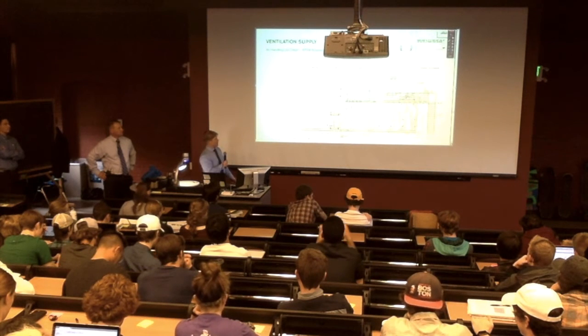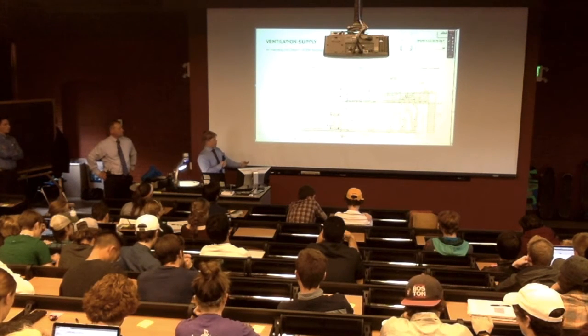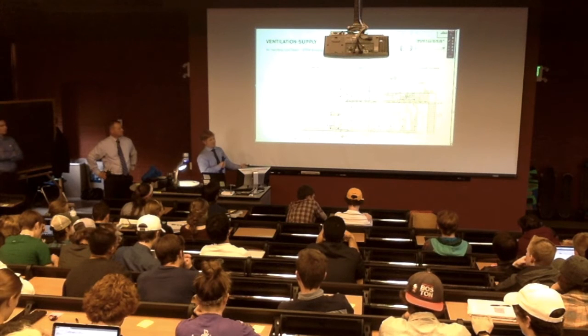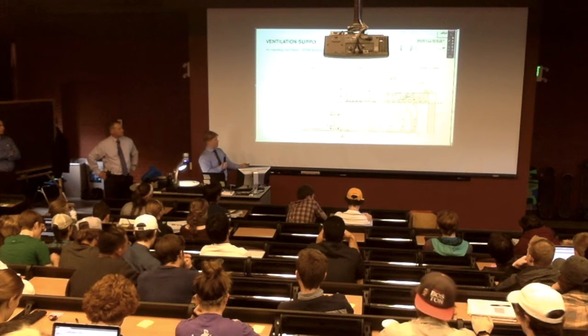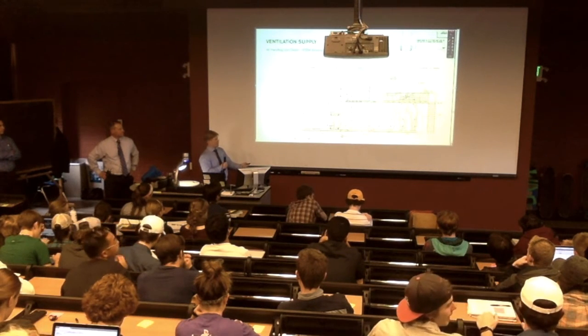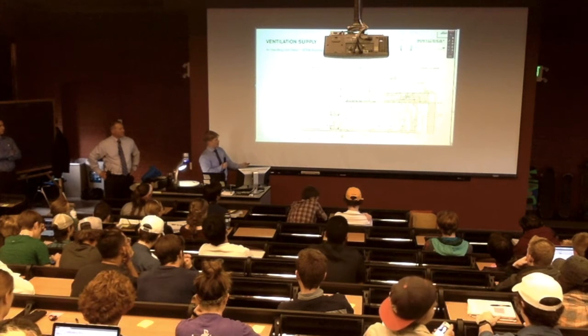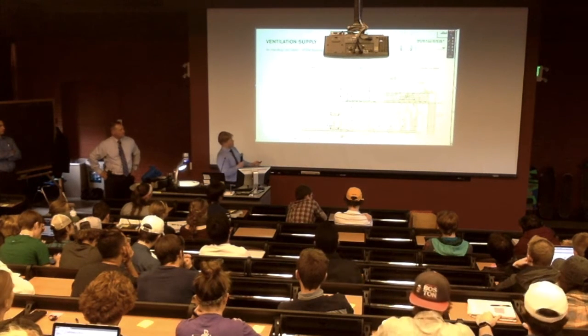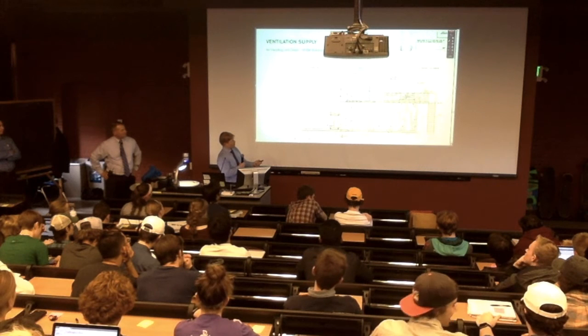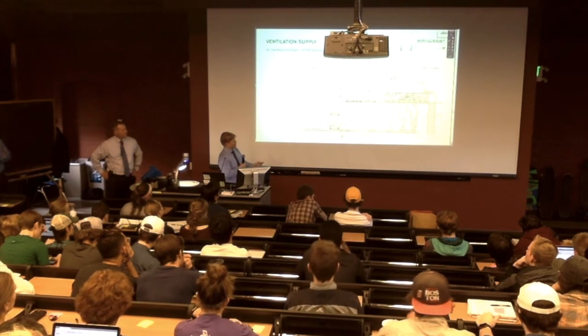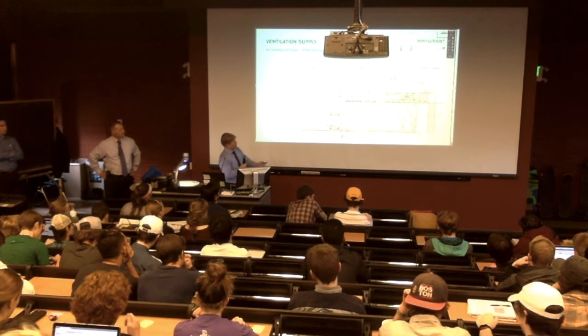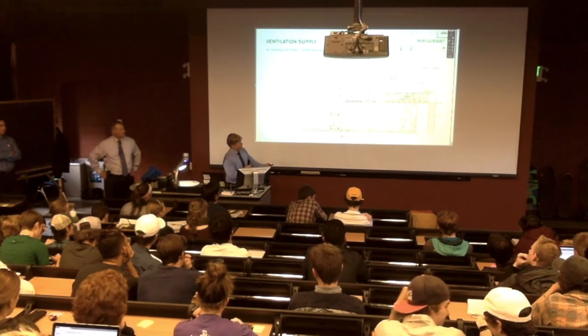and then from there you're blowing air through the coil. Coil's another static pressure loss. You need a fan to be sized to overcome the pressure drop from blowing the air through a coil. In this particular unit we have 3 separate coils. Actually, I'm going to go from where the air comes in the unit on the supply side.